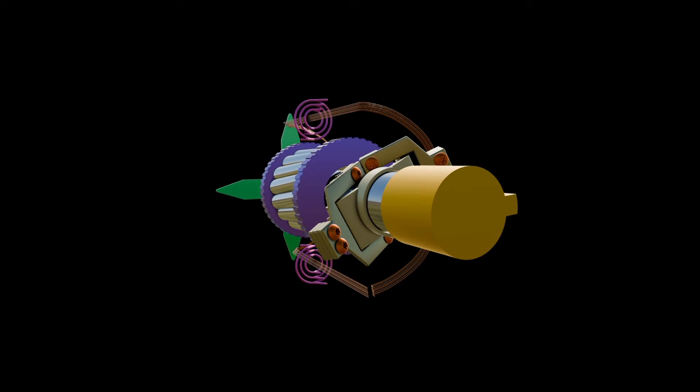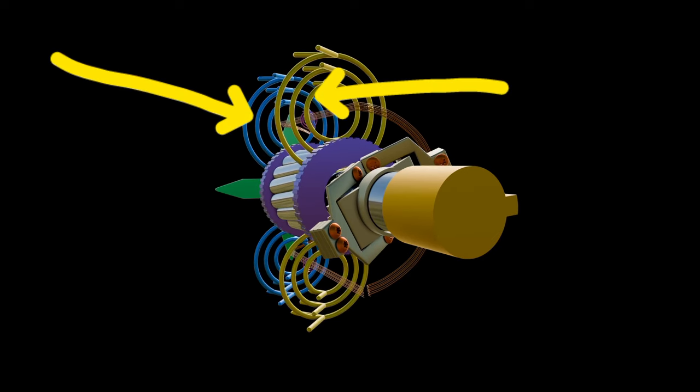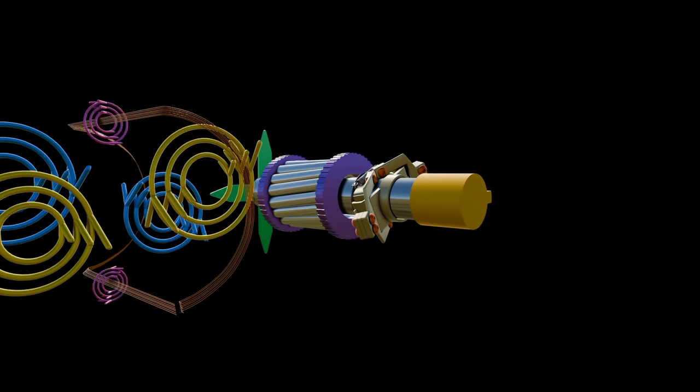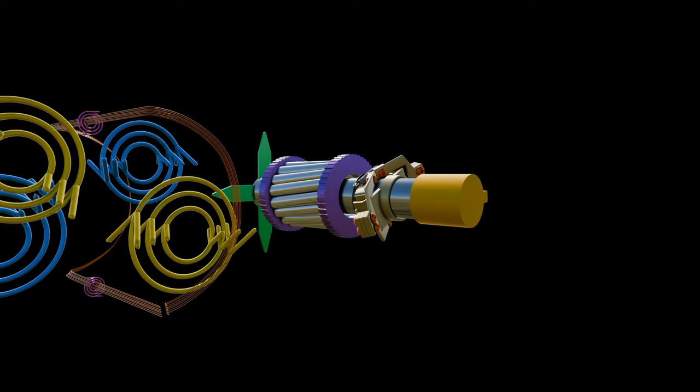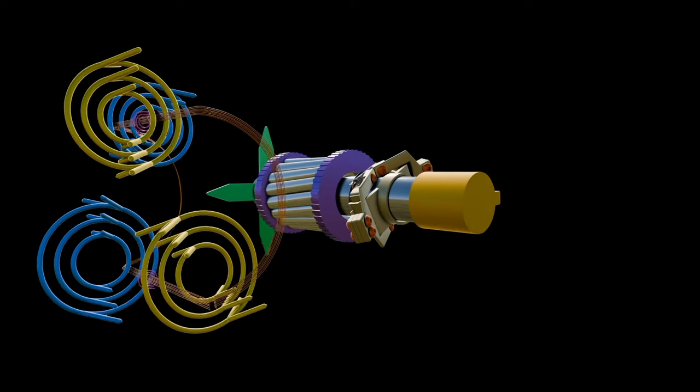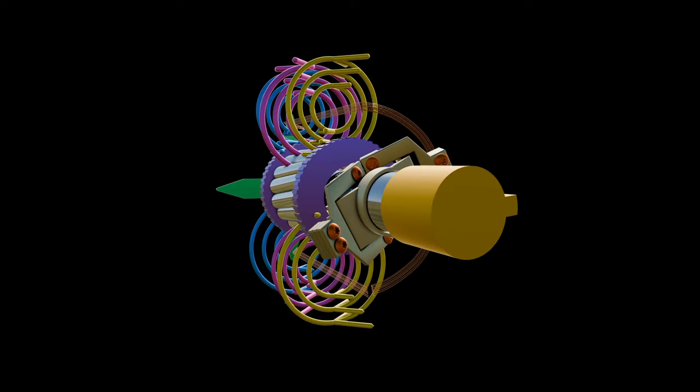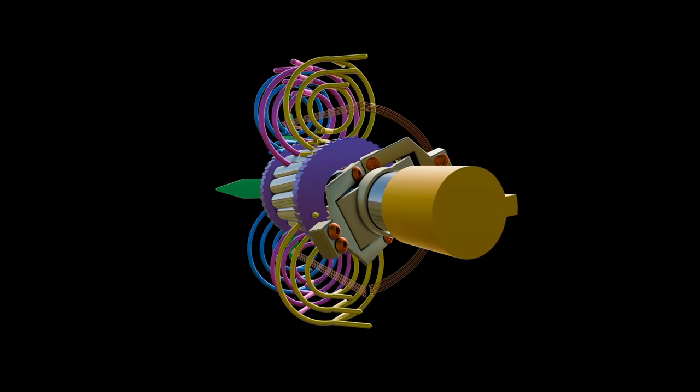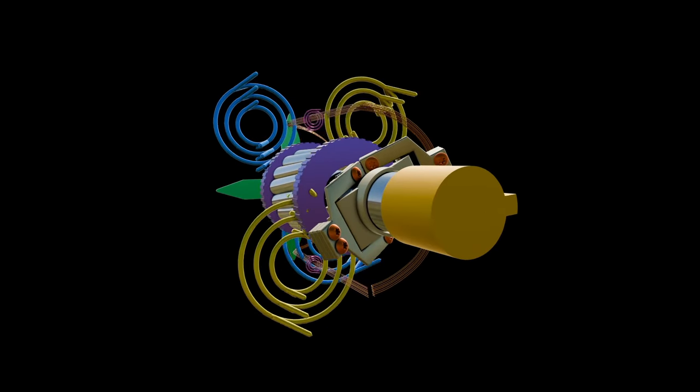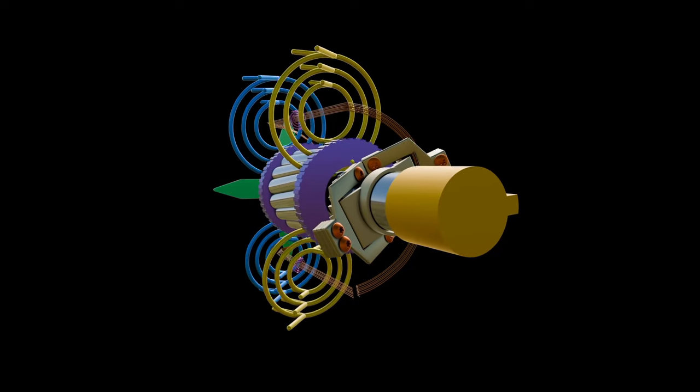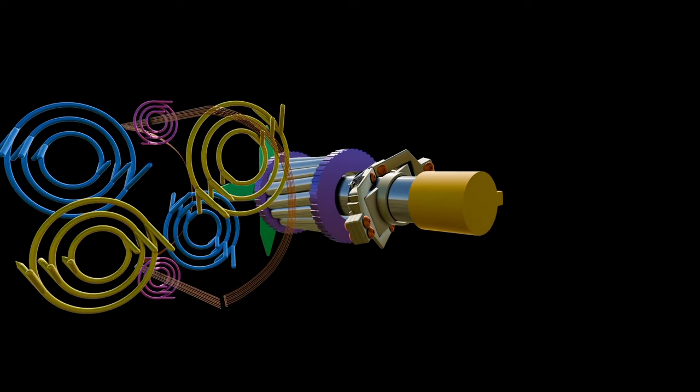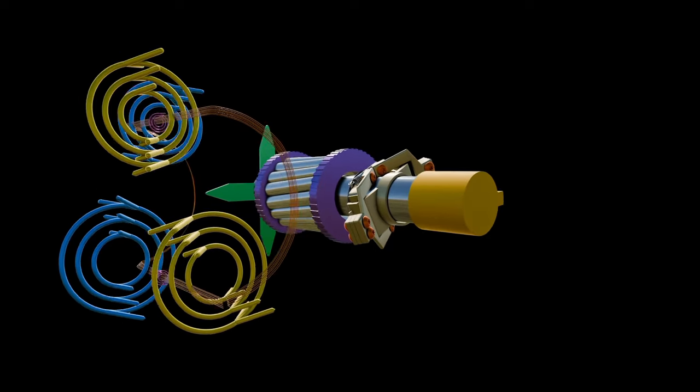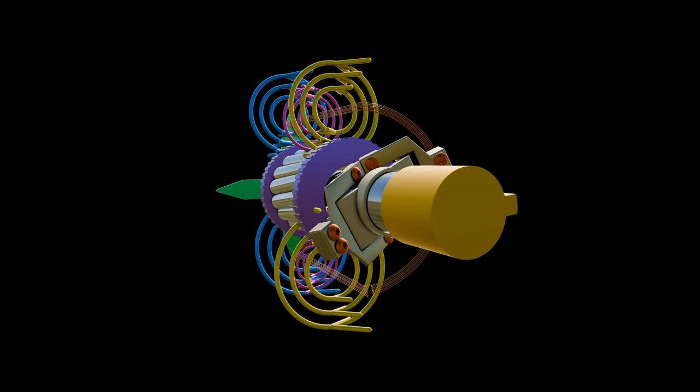I have represented this by two separate revolving blue and yellow magnet fields, with one revolving clockwise and the other anticlockwise. Here the sum of these two separate revolving fields is equal to the initial alternating field. This is because of double-field revolving theory. Hence forces induced by single-phase AC supply on these windings are equal and opposite. Hence, when trying to balance, the motor only vibrates.